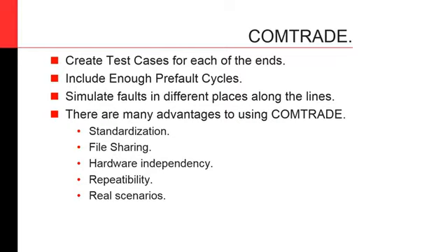Because the ComTrade files store the actual oscillography of whatever happens or is proposed to happen in the system, they can include the actual behavior of the power system, not just a steady state and another steady state, as we had with the states playback: the pre-fault, fault, and then post-fault.